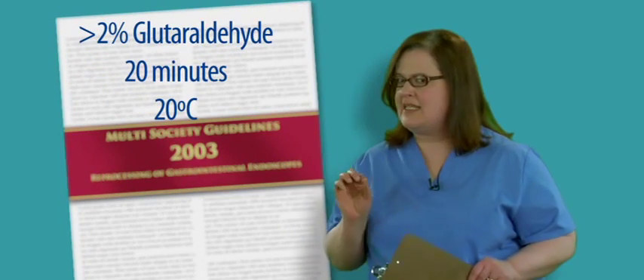The 2003 Multi-Society Guideline for Reprocessing of Flexible Gastrointestinal Endoscopes is a position statement which speaks to the process and issues related to the reprocessing of flexible gastrointestinal endoscopes. With this, the issue of exposure times and temperatures of FDA-cleared high-level disinfectants and sterilants are discussed. The Multi-Society Guideline reports that multiple scientific studies and professional organizations support the efficacy of greater than 2% glutaraldehyde at 20 minutes at 20 degrees Celsius. For other solutions, consult the manufacturer's label instructions.